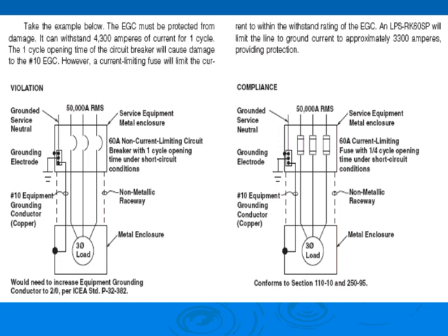What they're saying here is, because you allowed the short circuit to sit on this number 10 for a cycle, you have to up the number 10 to 2/0, option 1, or you have to increase the speed of this circuit breaker to a quarter of a cycle. How would you increase the speed of a circuit breaker to a quarter of a cycle? You can't. You basically redesign the circuit breaker, right? Or replace it with a fuse.